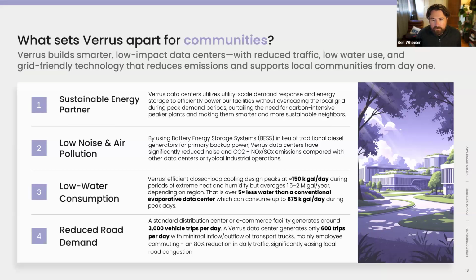On water, we've focused on low water consumption. We've got closed-loop air chiller systems, not evaporative cooling. We do use a little water to help chop the peaks off on some of the hottest days of the year, but it's minuscule compared to a conventional evaporative cooling data center. We also have reduced road demand, comparing a general data center to a distribution center, for example—data centers don't have a lot of traffic going in and out. It's just electricity going in, and information and heat coming out.